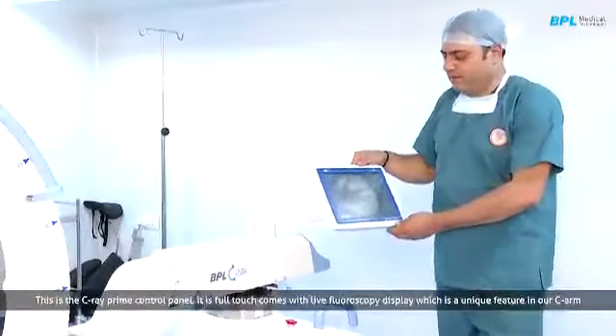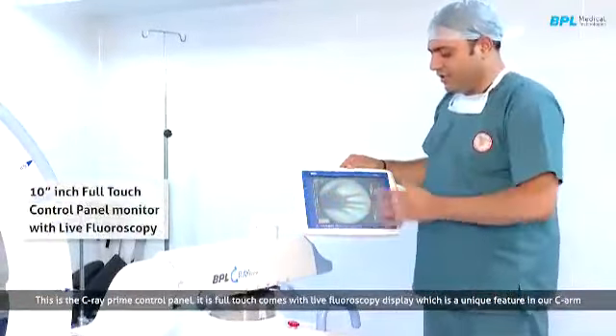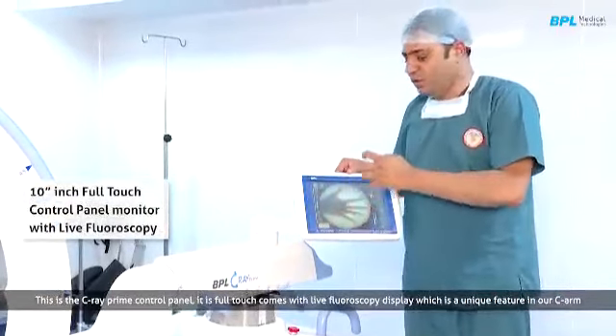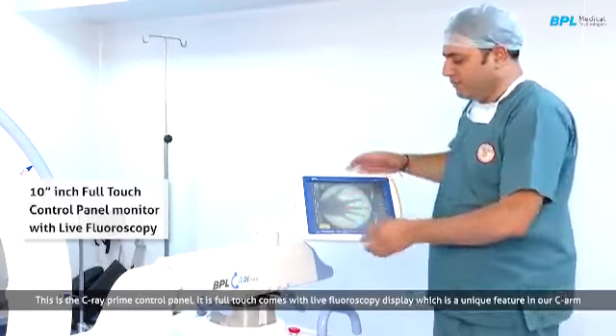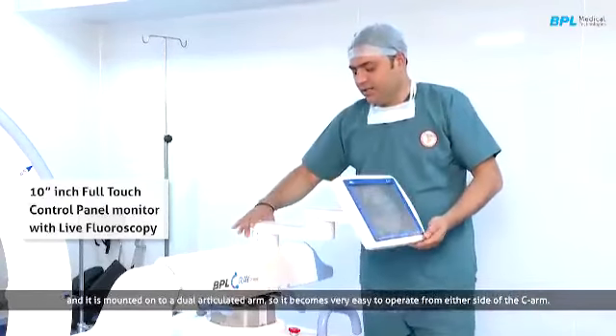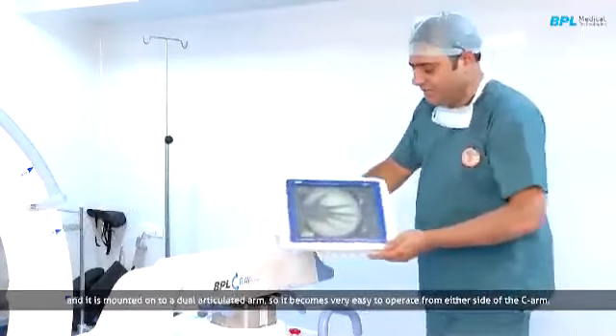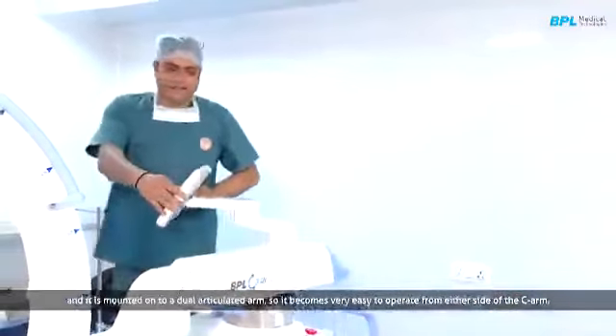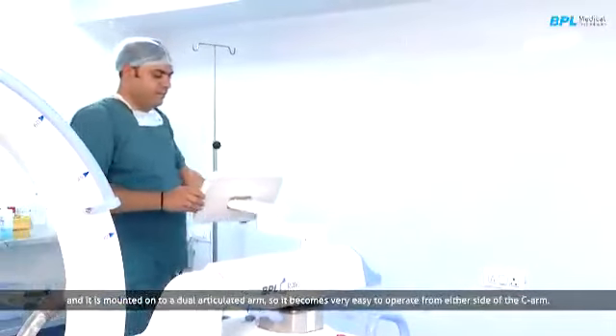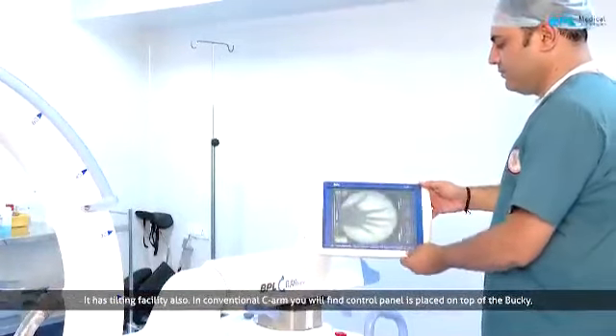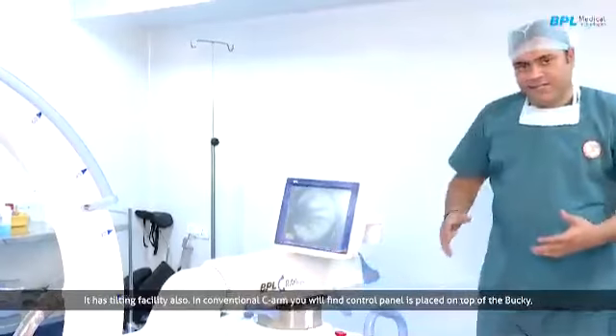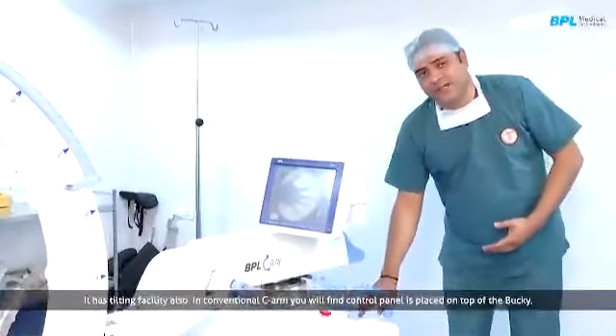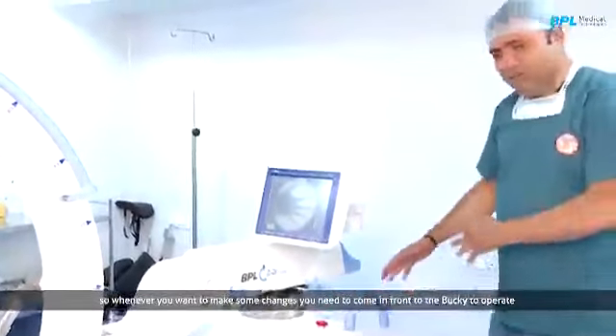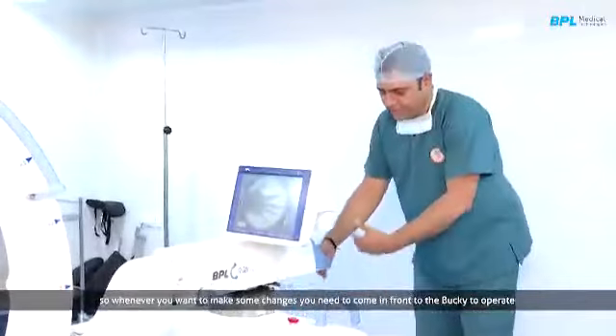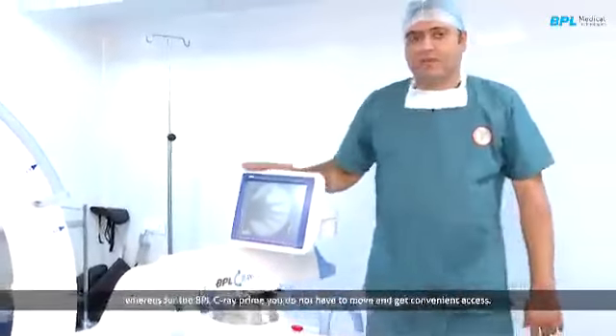This is the C-Ray Prime control panel. It is full touch, comes with live fluoroscopy display, which is a unique feature in our C-arm, and it is mounted onto a dual articulated arm, so that it is very easy to operate from either side of the C-arm, and it has a tilting facility also. In a conventional C-arm you will find the control panel is placed on top of the Bucky. So every time you want to access features, you have to come just in front of the Bucky and operate, which is not the case with C-Ray Prime.